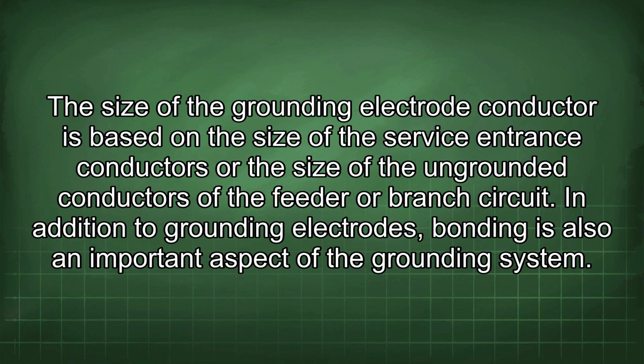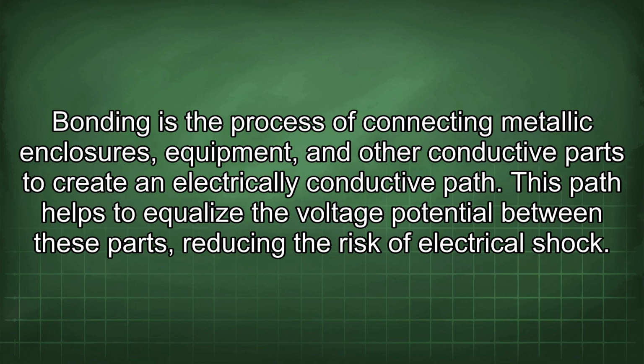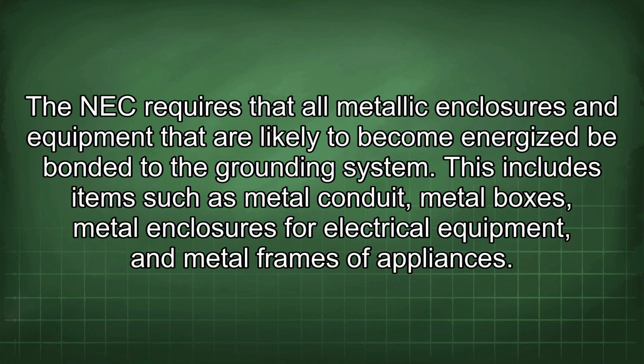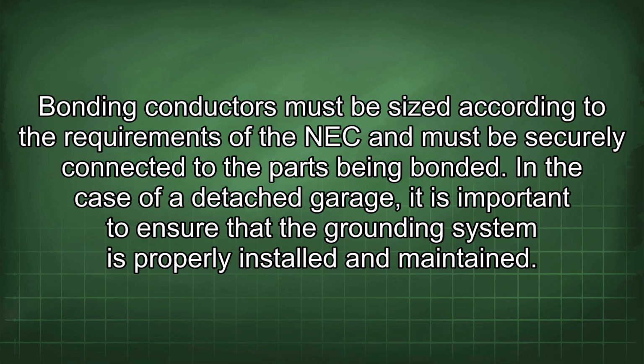In addition to grounding electrodes, bonding is also an important aspect of the grounding system. Bonding is the process of connecting metallic enclosures, equipment, and other conductive parts to create an electrically conductive path. This path helps to equalize the voltage potential between these parts, reducing the risk of electrical shock. The NEC requires that all metallic enclosures and equipment that are likely to become energized be bonded to the grounding system. This includes items such as metal conduit, metal boxes, metal enclosures for electrical equipment, and metal frames of appliances.